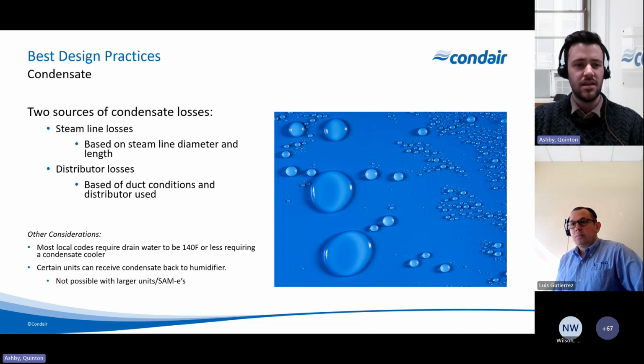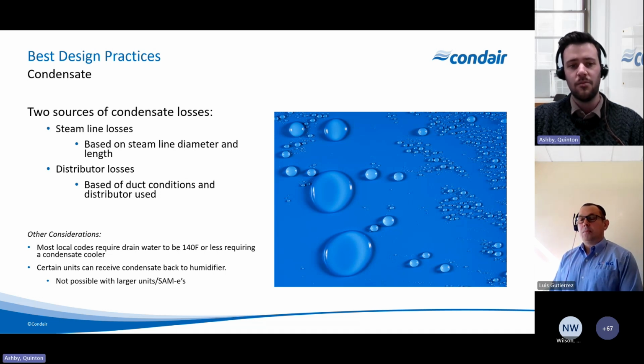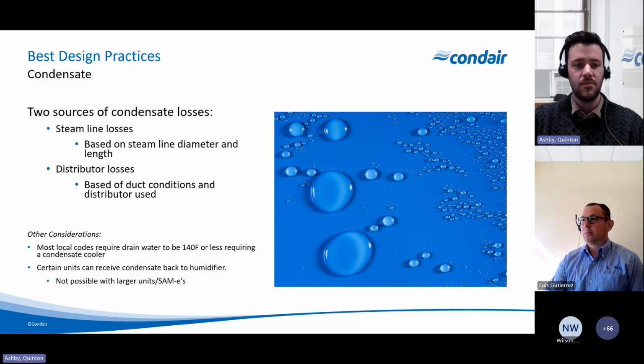Some other quick considerations: most local codes require drain water to be 140 or less. This typically requires a condensate water cooler. All of our own units have internal drain water cooling, but the condensate is a little bit different. Certain units can return that condensate back to the humidifier. However, it's important to note that in scenarios with larger capacities, as well as our steam short absorption manifold, which is a fairly large manifold, it produces too much condensate and it has to be sent to drain. So, important things to consider in terms of condensate.